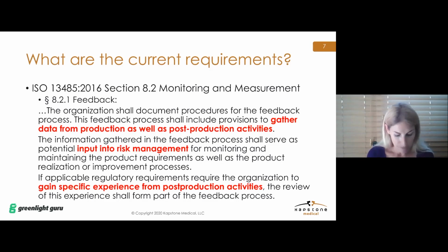Annex 2, Section 3.2. Section 8.2 of ISO 13485 specifically states, the organization shall document procedures for the feedback process. This feedback process shall include provisions to, and this is important, gather data from production as well as post-production activities. This information will serve as a potential input into risk management. If applicable, regulatory requirements require the organization to gain specific experience from post-market activities. So I'm just hitting on some of the highlights. You will all receive copies of these slides and you can review them in detail if wanted. So during your conversion to 2016, organizations will have been required to implement some of these systems already.